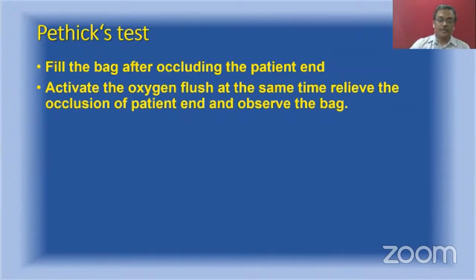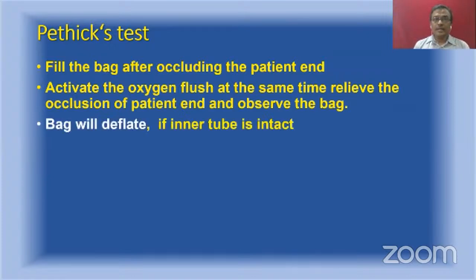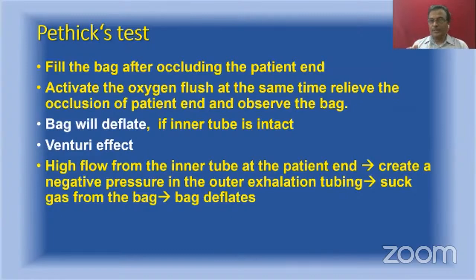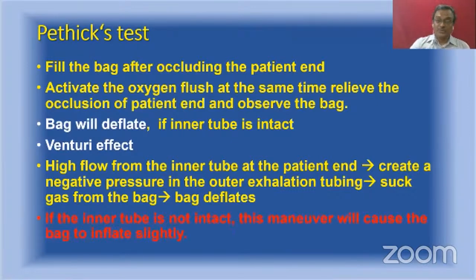What is going to happen to the bag? The bag will deflate if the inner tube is intact. What is the mechanism by which the bag is deflating? This is because of the Venturi effect. The high flow from the inner tube at the patient end will create a negativity at that area. And when negative pressure is developing, that will suck the gas from the bag and the bag will deflate. Suppose you see that the bag is inflating slightly, that means your inner tube is not intact. There is some problem with your circuit.